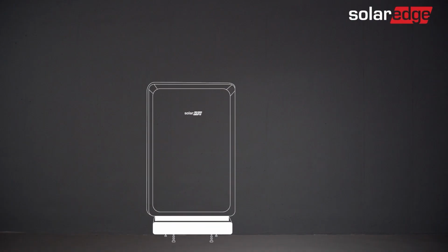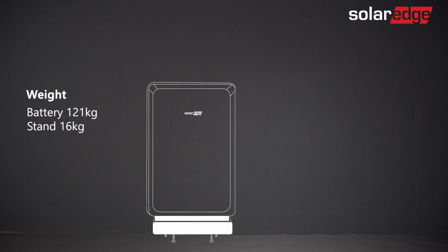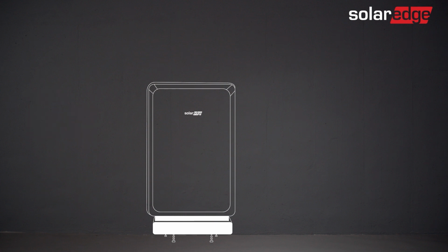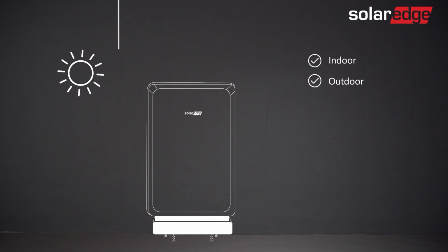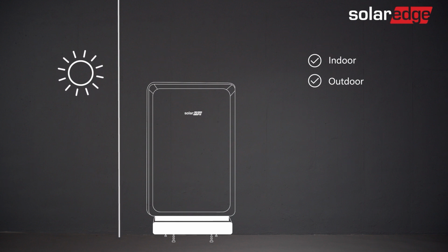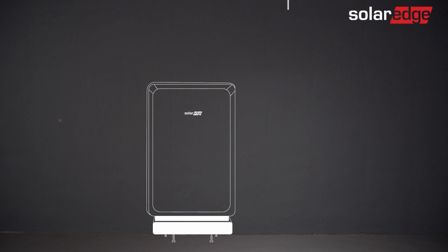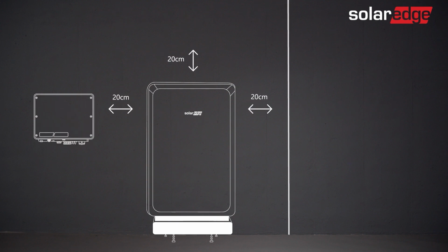Our first step is to determine a suitable location for the battery installation, one that can withstand the weight of the battery and also takes into account local safety regulations and building codes. The SolarEdge Energy Bank is both indoor and outdoor rated. If installed outdoors, we advise keeping it away from direct sunlight and extreme temperatures. Also, note the required clearance between the battery and other objects on the wall.